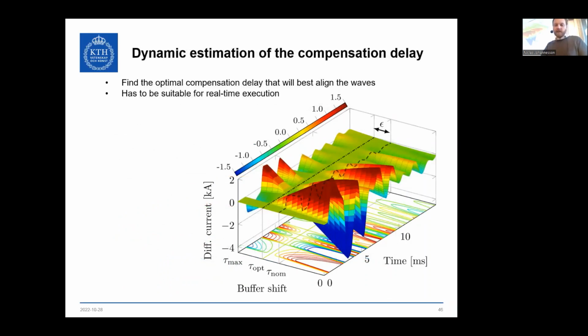If you plot this, you get the compensation delay you would need to wait before performing the calculation, while waiting for the telecommunication to arrive. If there's an error, the nominal time delay causes some differential current that isn't zero, whereas if you find the optimal compensation delay, everything is smooth sailing.